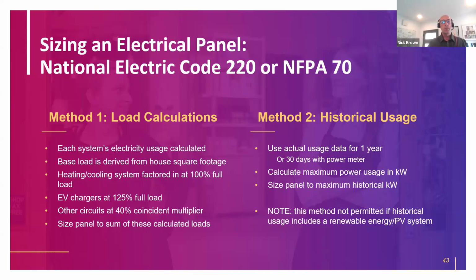Then there are coincident multipliers: things like your water heater and garbage disposal get factored in at 40%, because they're not going to run all concurrently. So you can put more amperage in your house than the maximum rating of your panel. Put another way: let's say you open your panel and it says 100 amps, then you start adding up the amps of the circuits—30 for HVAC, 20 for your oven—and pretty soon you're over 100. That would be an incorrect approach to sizing your panel because of this coincident factor; many of those circuits only get valued at 40%. Finally, you sum up all those calculated loads, and that's what you design your panel to.